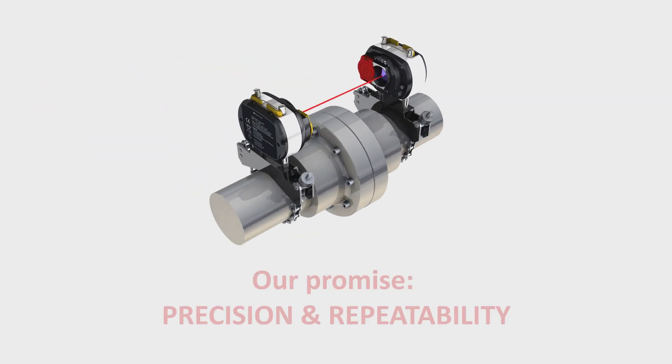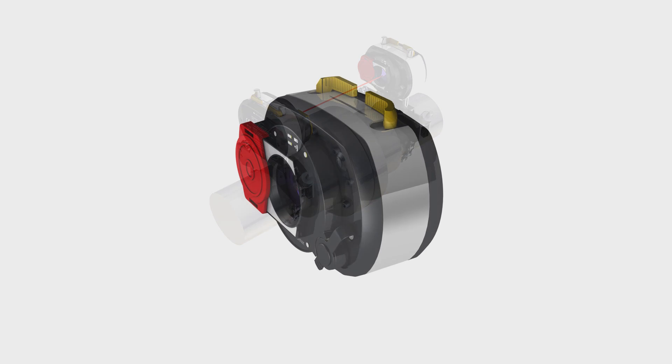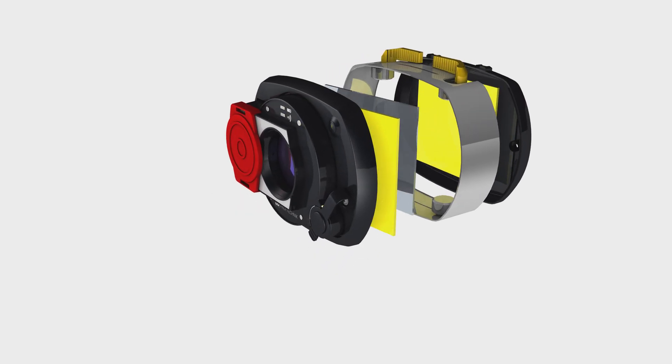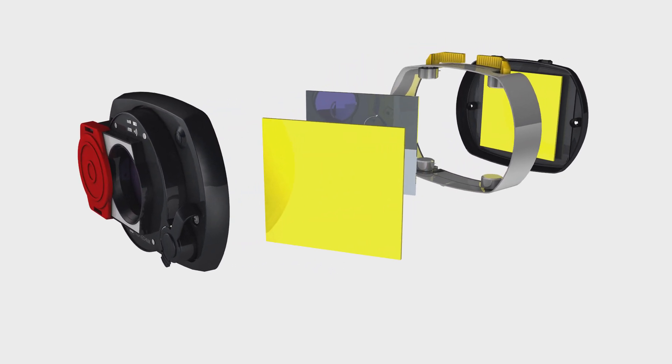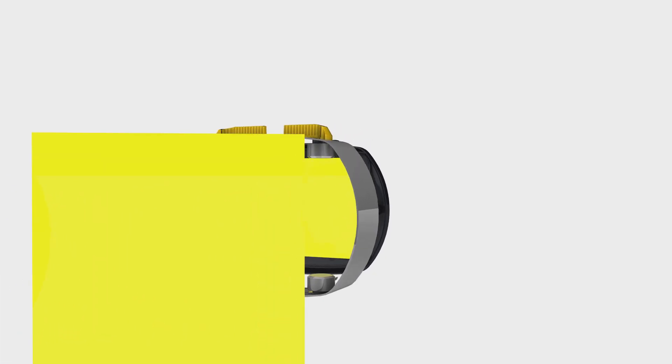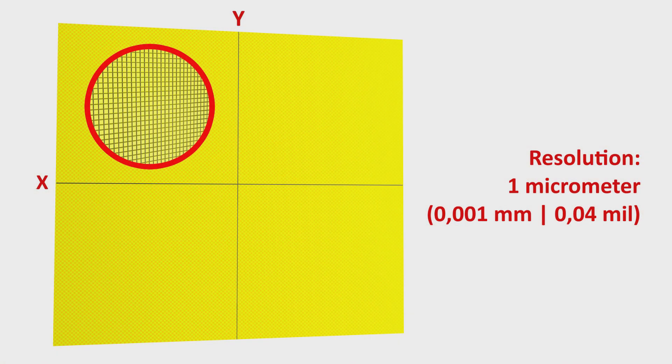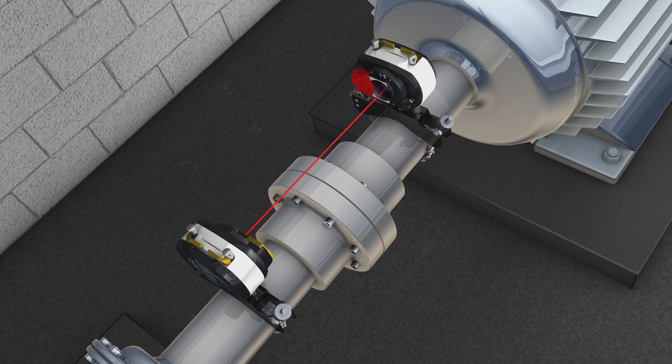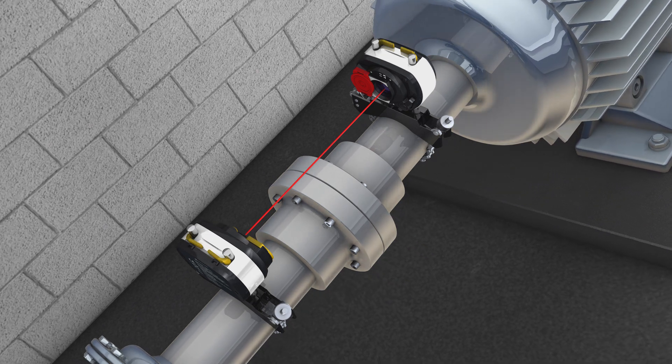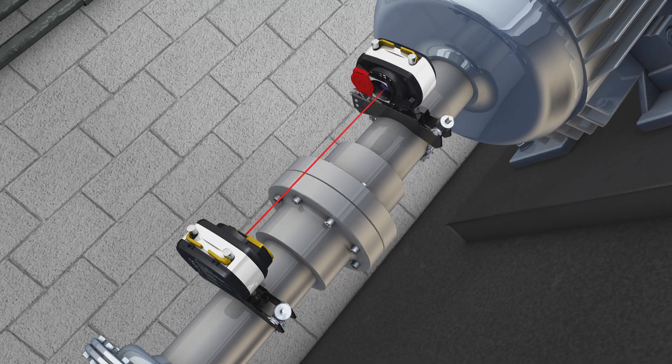Now let's see and understand how precise Pruftechnik SensALIGN detectors are. The resolution of each detector is at 0.001 millimeter, that means 1 micrometer. And since the detector areas are given in X and Y axis, Pruftechnik SensALIGN technology is able to measure shaft angularity and offset in one single shaft rotation.